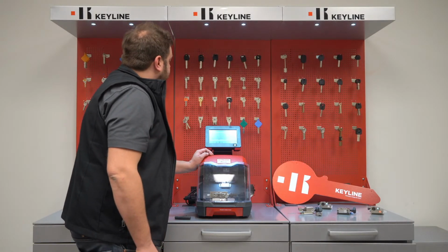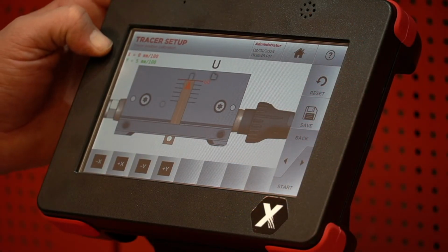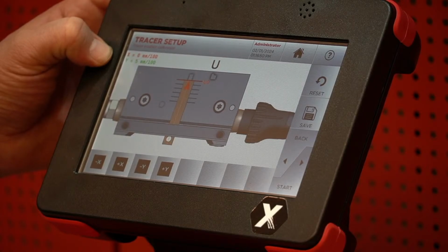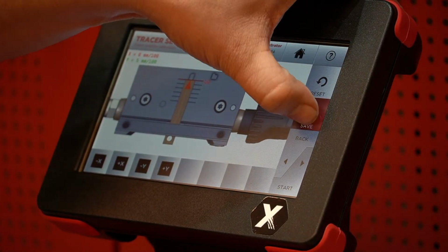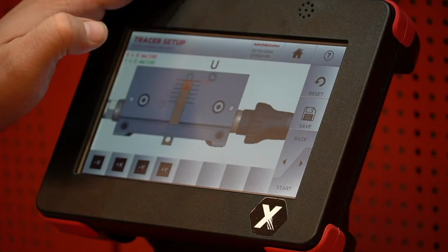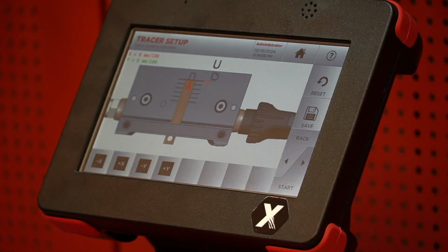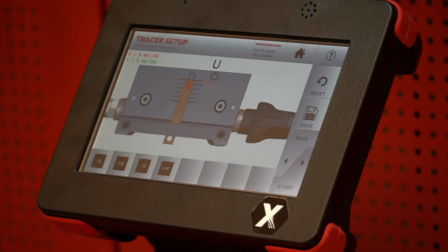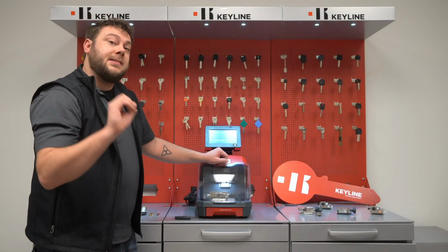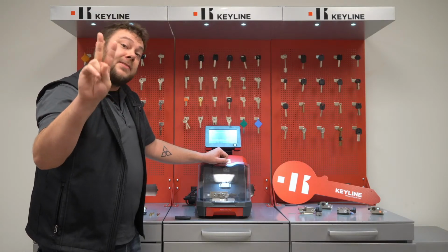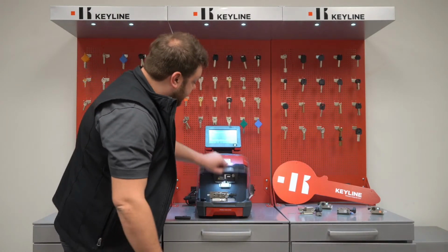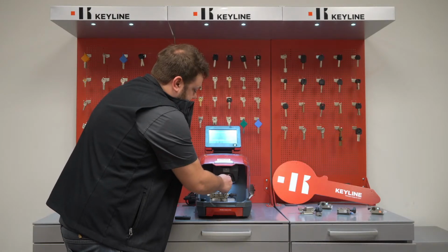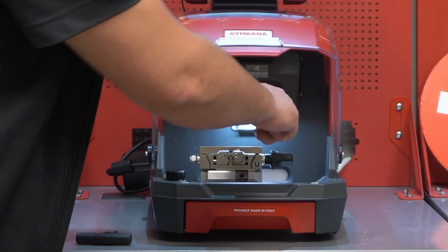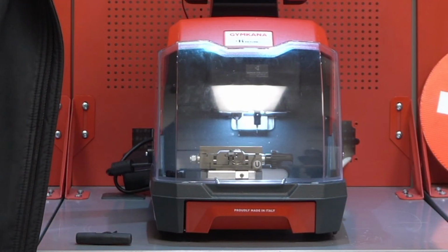This changed a little bit, and X went from 1 to 0, and our Y went from 10 to 5. So you're going to hit save, hit yes, and tracer setup is calibrated if it's within plus or minus 2 of your previous calibrations. So our X was okay, our Y was not. It went from 10 to 5, which is a differential of 5 instead of 2. So to be safe, I'm going to drop the tracer knob down, lock it in position. I'm going to run it one more time after I save.